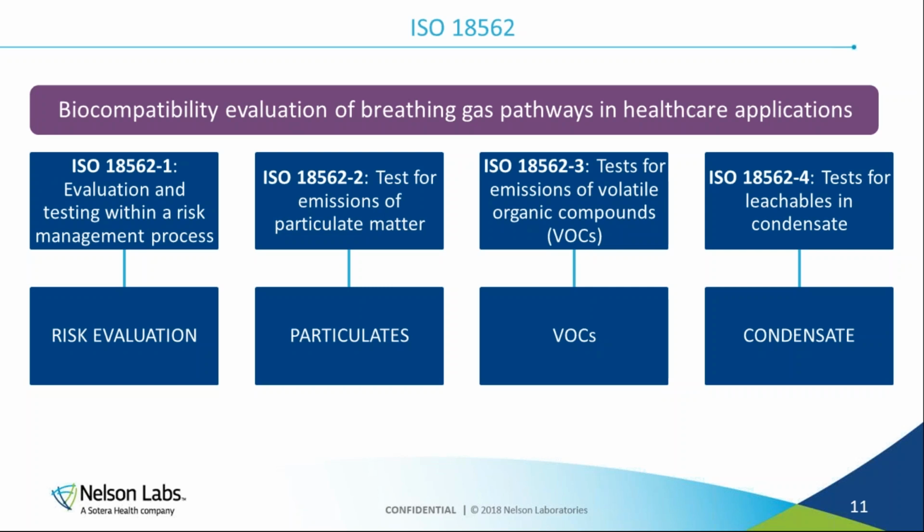So part 2, we're going to assess particulates. Part 3 will be volatile organic compounds, or VOCs. And then part 4 is tests for leachables in condensate. We'll go through each one of these to understand how they apply to specific devices and the testing that's recommended within these standards.